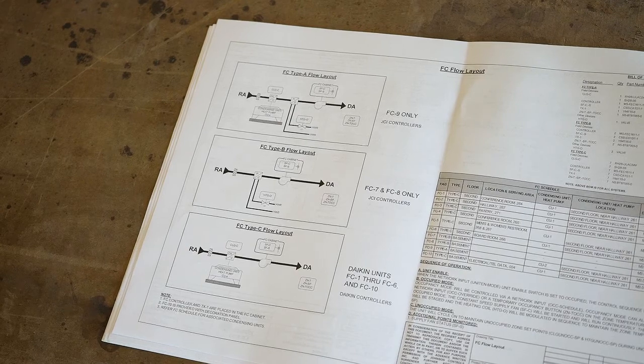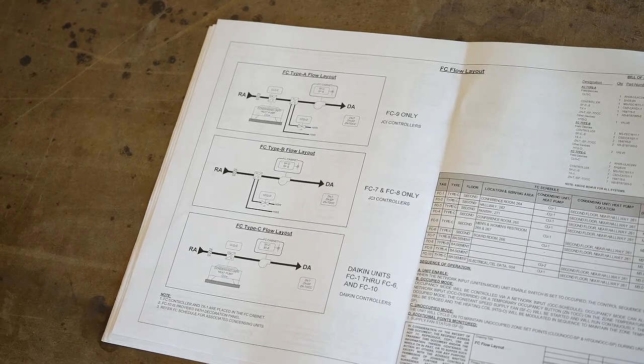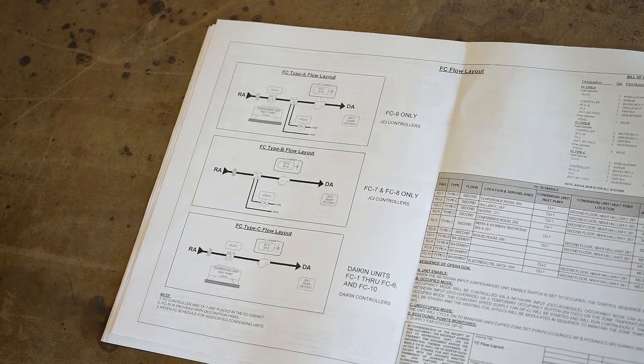So those are little things. And we'll go through and, is the plate located up high where it can be? Nope, it's located at the same height as the rest of the thermostats in the building. And we'll go through and we'll show you where those are at. Because if you did locate it up higher, you're going to get a false reading on it, yeah.